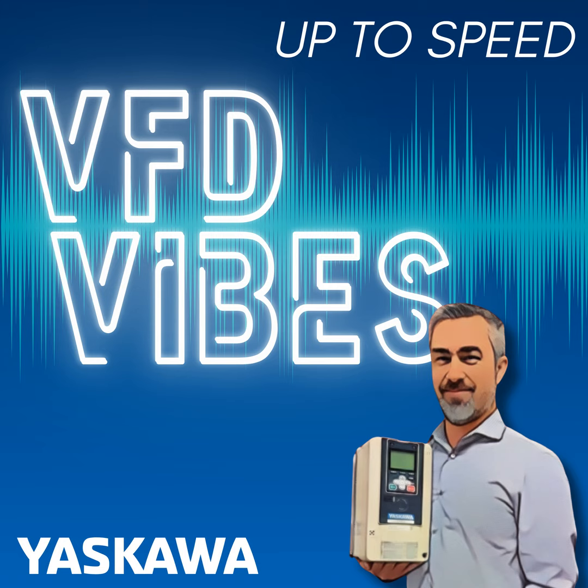In startup, this is very useful to make sure you have both a run command and speed reference, otherwise your motor will not turn. Assuming we have verified both of these requirements, what if we are still not able to get the drive to run? What if we have faults keeping us from running or tripping soon after we start running?